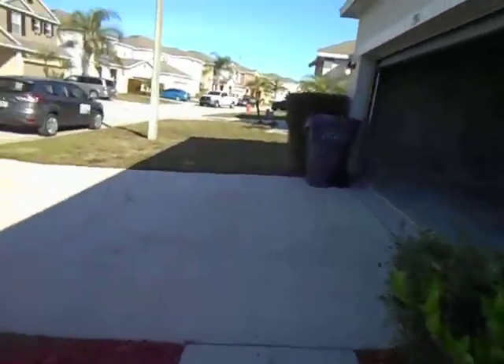As we head back into the garage, we took a look at the electrical panel. Your sub-panel is located on the east side of the garage. When you look at it, the copper wires are bright and shiny, your main service entrance wires look very good, neutral wires are at their bus bar, ground wire is at its bus bar, and all the breakers and service conductors look good. The branch wiring looks good.